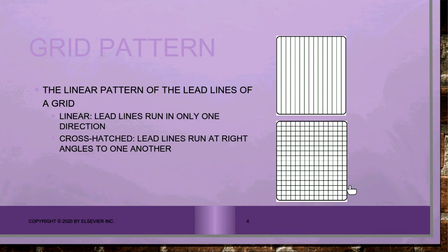Okay, this cross-hatched grid. And then in 1920, Hollis Potter came along and realized that if you remove that second set of lead strips and only have the lead strips running in one direction, you can manipulate the grid and the positioning a little bit better because you're not always going to be running into the lead lines. He also realized that if you removed one set and added motion to it, you could blur out the grid lines that were left so that they wouldn't show as artifact on the final image or radiograph.